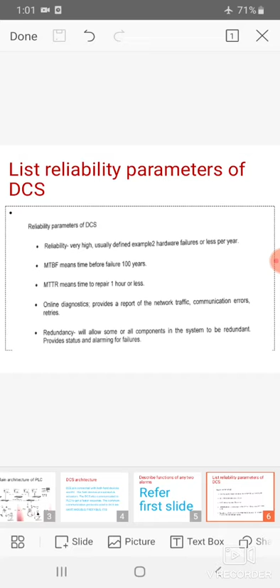Then coming to list the reliability parameters of the DCS. First, reliability is very high, usually defined as 2 hardware failures or less per year. That is, in a year a maximum of 2 hardware units may fail. That is the guarantee condition we are giving. Then MTBF, mean time between failures, 100 years. MTTR, mean time to repair, 1 hour or less.